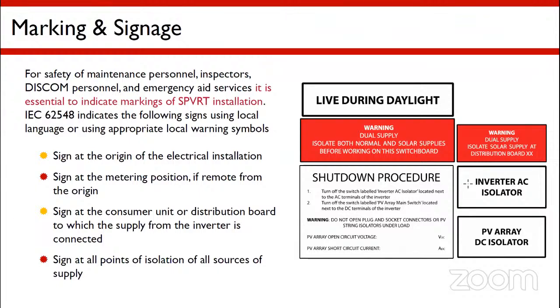There will be only one switch, the AC MCB on the AC side, so first the load has to be disconnected. That's why the person goes and turns the AC MCB off. Once the AC MCB is off, the load current becomes zero, and once the load current is zero, that is the safe time to switch off the DC side.